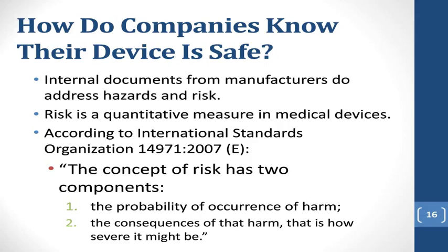Risk with medical devices is actually a number, and it's a combination of a probability, how likely is it to occur, and then what are the consequences. So I will show you further on some examples of risk matrices or risk tables, and when you review documents, you will likely see these things.